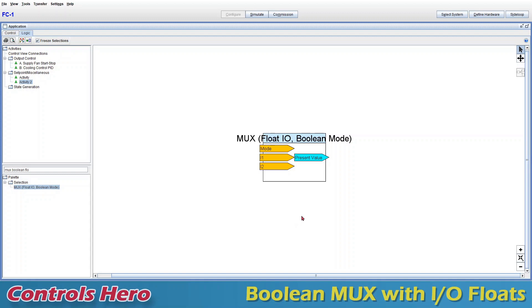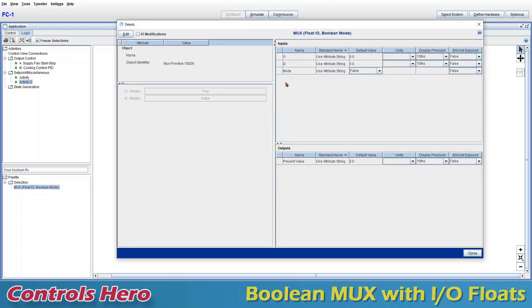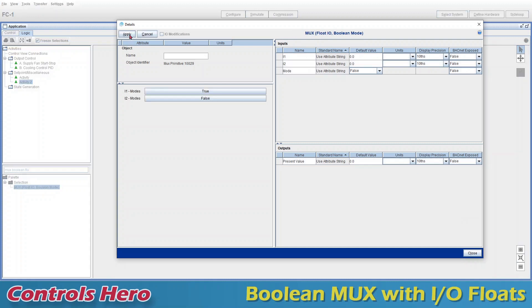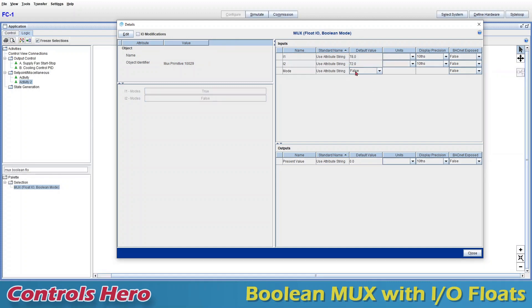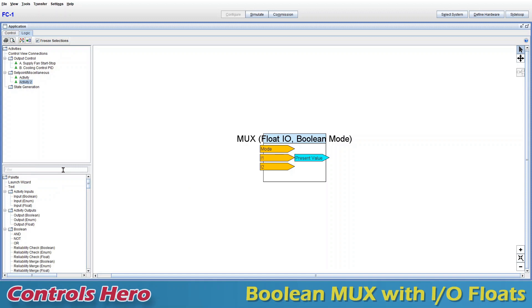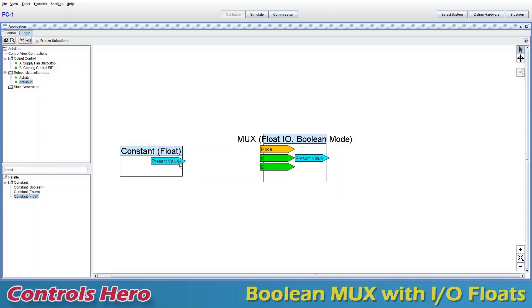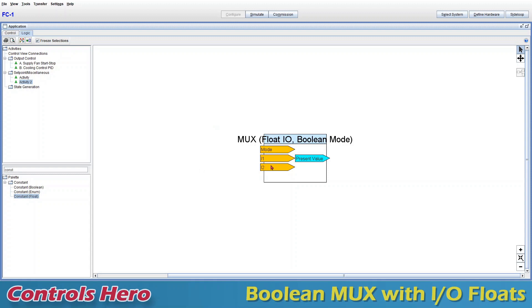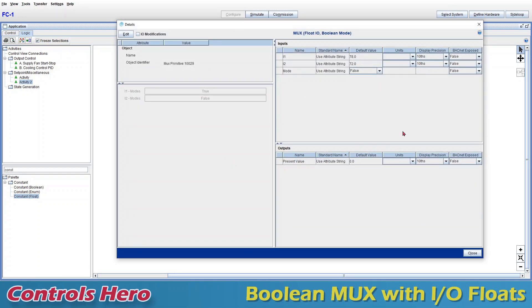Now I want to show you a trick you can apply to any module. If you double-click and go to the right-hand side under Inputs, you'll see I have input 1, input 2, and mode. You can actually put a value directly there — for I1 I can set it to 78, and I2 to 72. That way you don't have to create a separate constant float and connect it. You can delete the wired constants and your values are still there — it's like a little shortcut.